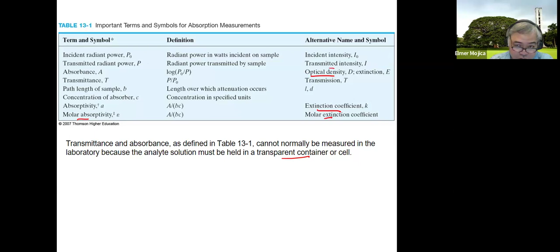Now, if you're going to look at the typical process that is happening in a glass cell, we could say we have reflection and scattering losses. This is usually the sample cell, your cuvette. Reflection can occur at two air-wall interfaces as well as two wall-solution interfaces. So this is the air-wall interface, one here and another one here, and then the wall-solution interfaces. Usually the resulting beam attenuation is substantial: about 8.5% of a beam of yellow light is lost by reflection in passing through a glass cell containing water. In addition, there's also attenuation of the beam that may occur as a result of scattering by large molecules and sometimes from absorption by the container walls.